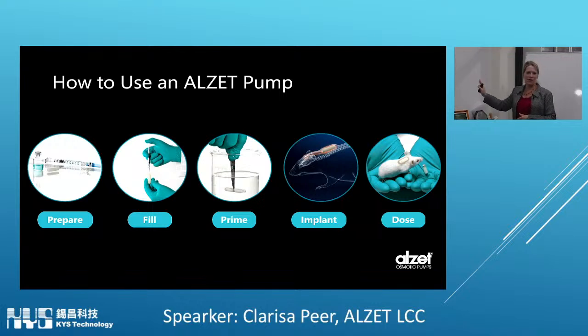Someone pointed out, actually on our trip here, that it would be nice to consider one more step, which is at the end, after you finish the infusion, what do you do? We do recommend that you take out the pump and check it, and even measure the solution remaining inside the pump, just to confirm that what's remaining is what you expected based on your calculations.